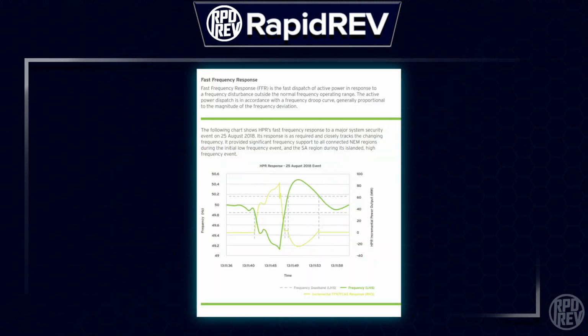Another function the Hornsdale Power Reserve performs is called fast frequency response, which is very similar to system integrity protection — it's meant to keep the frequency of the AC power on the grid at the desired level, which in Australia is 50 Hz. Some contingency events can cause the frequency to dip, and the Hornsdale Power Reserve can act in about 100 milliseconds for frequency response and system integrity protection.